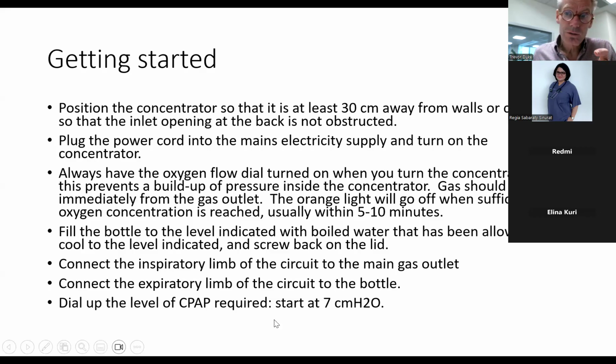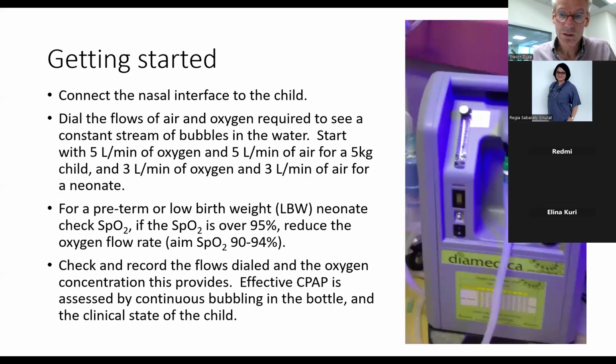So usually with the last two interfaces, the OptiFlow prongs and the soft nasal prongs, the wider bore prongs, you don't see auto bubbling, but it's just important to check that you don't see bubbling until you've attached it to the patient's face. You should start to see bubbling when you attach it to the patient's face. So you connect the nasal interface to the child, and then you dial up the air and gas flow until you see a constant stream of bubbles in the water.